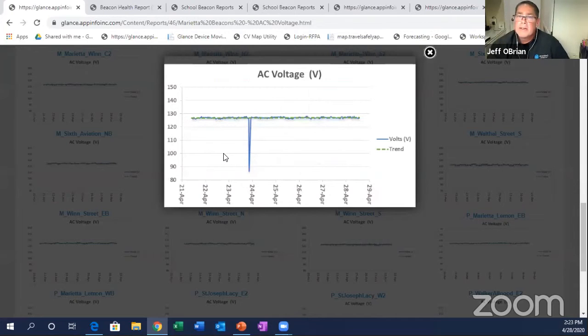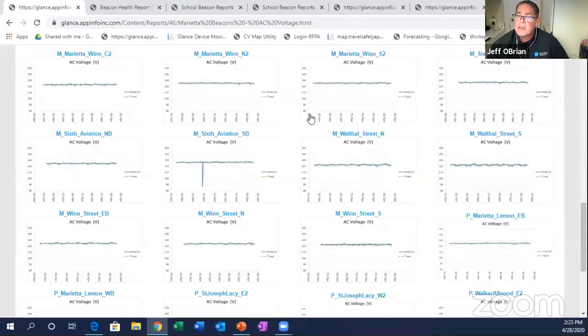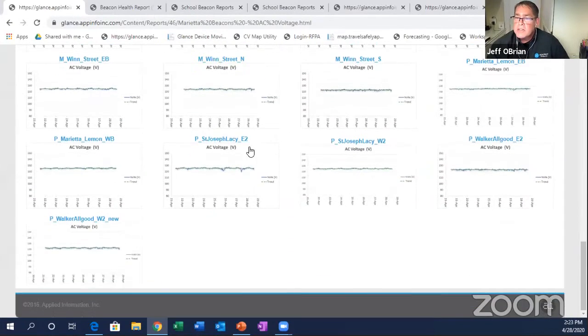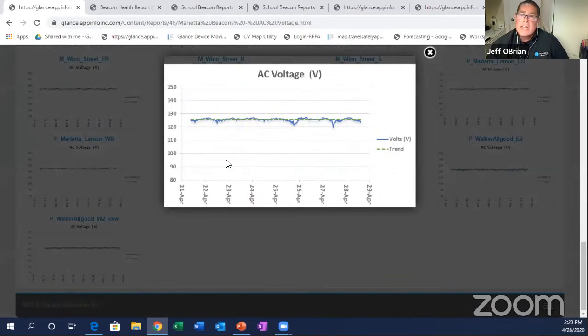Here in the south, we've had a number of storms come through over the last week or so, and this is a clear representation of having a little bit of a power outage over a period of time. So if we were seeing this happening consistently at a particular location, from a maintenance perspective, it's a nice way for the agencies to jump in there and tighten some settings, and make sure they're working with their local power company to get good, clean power at those locations.